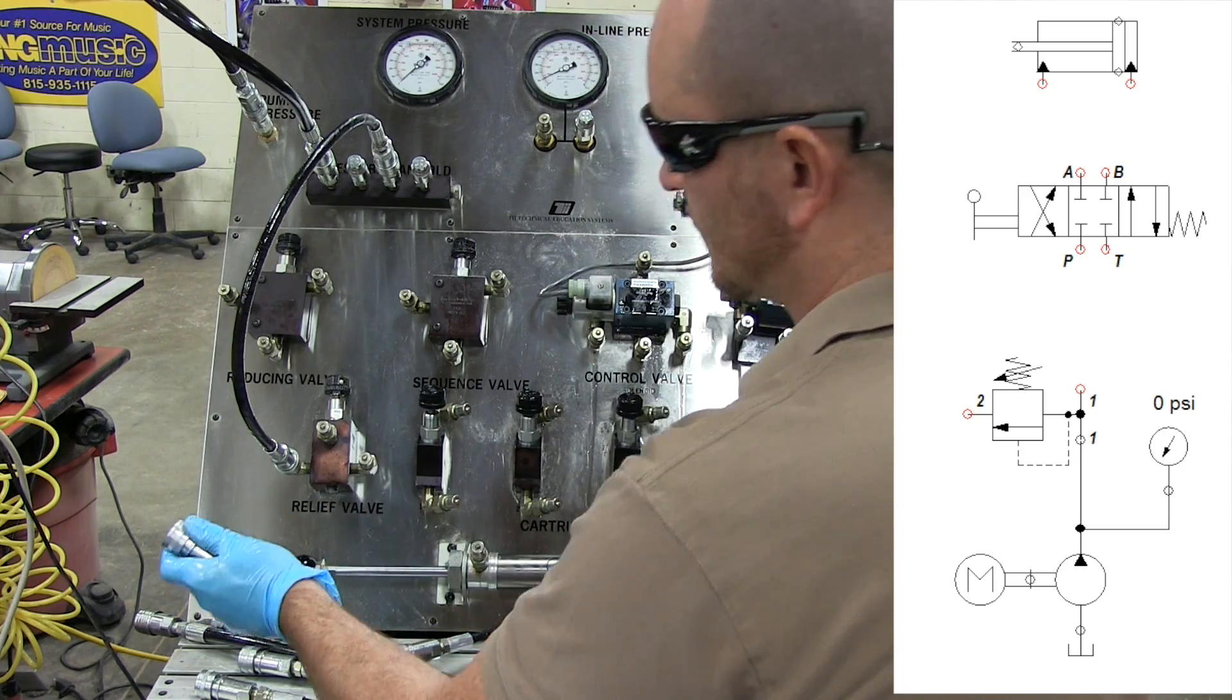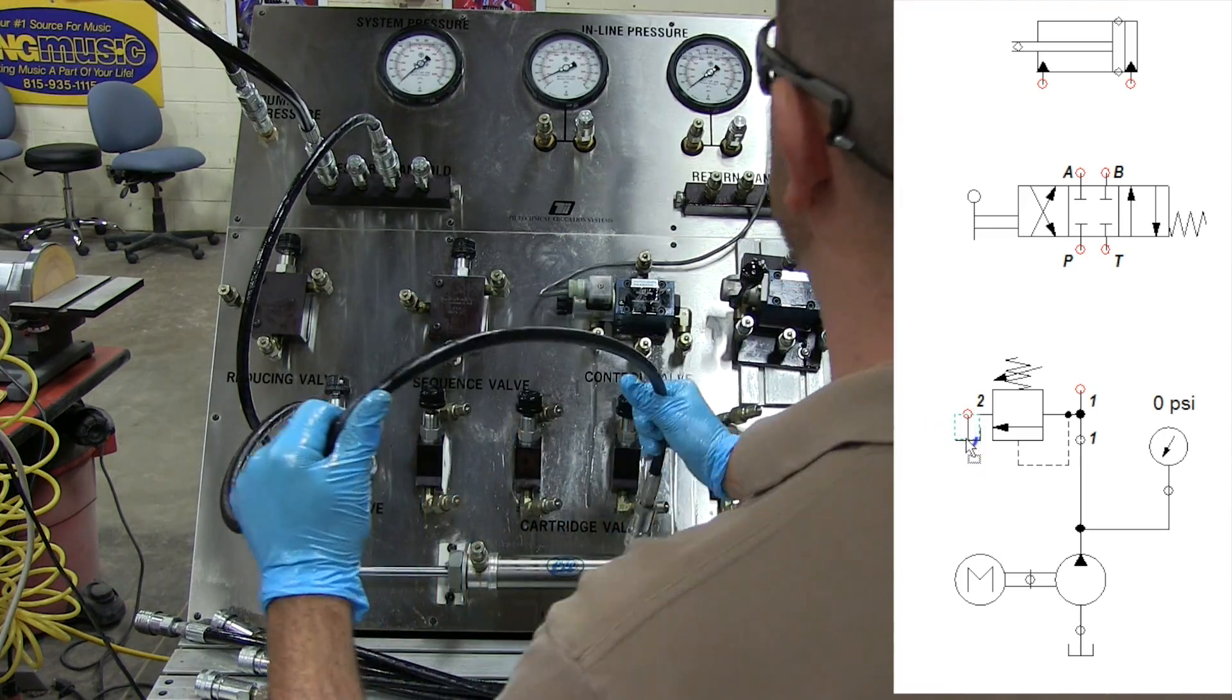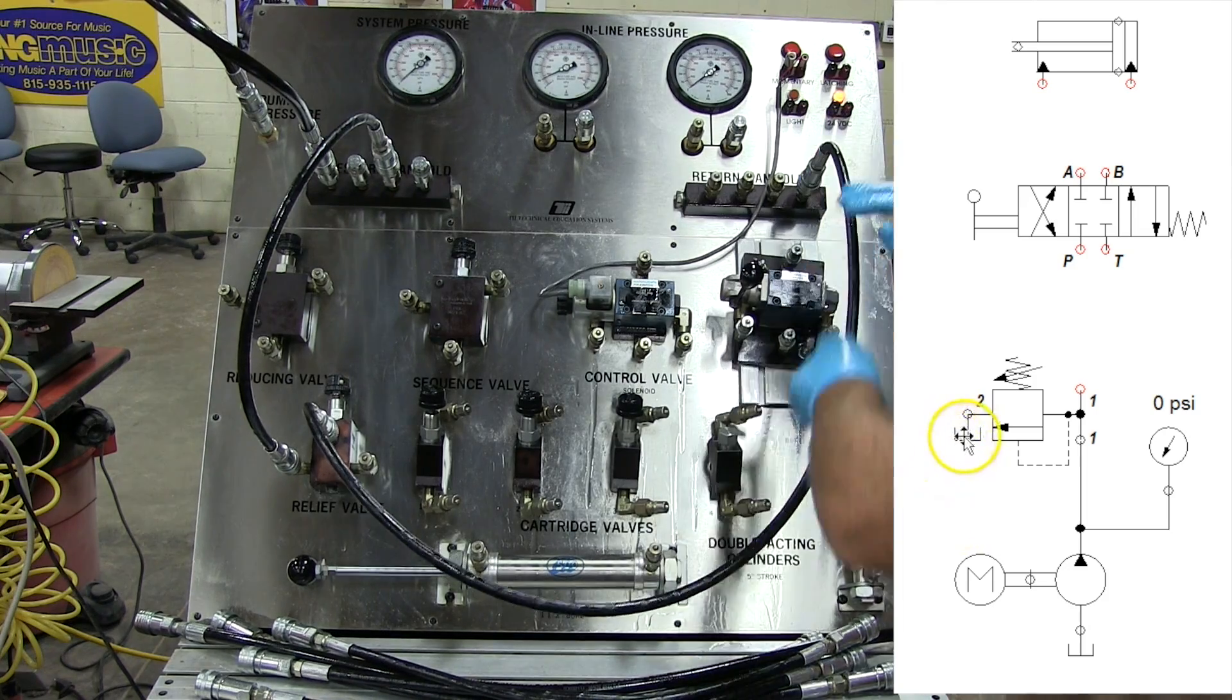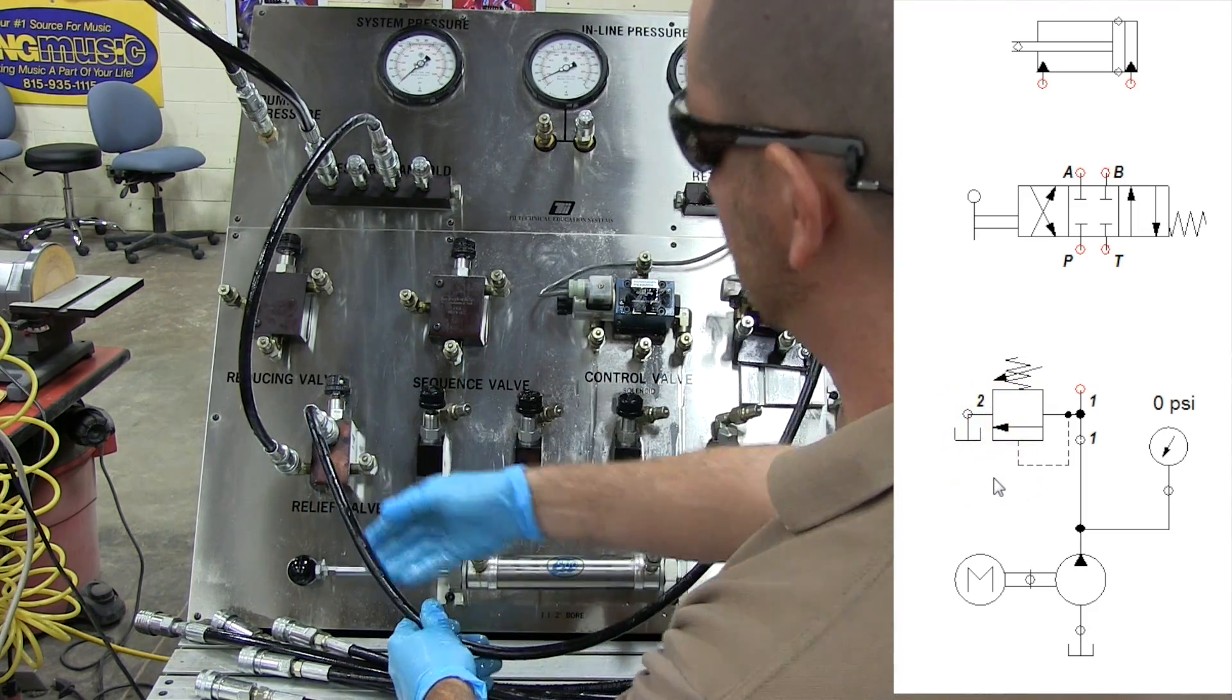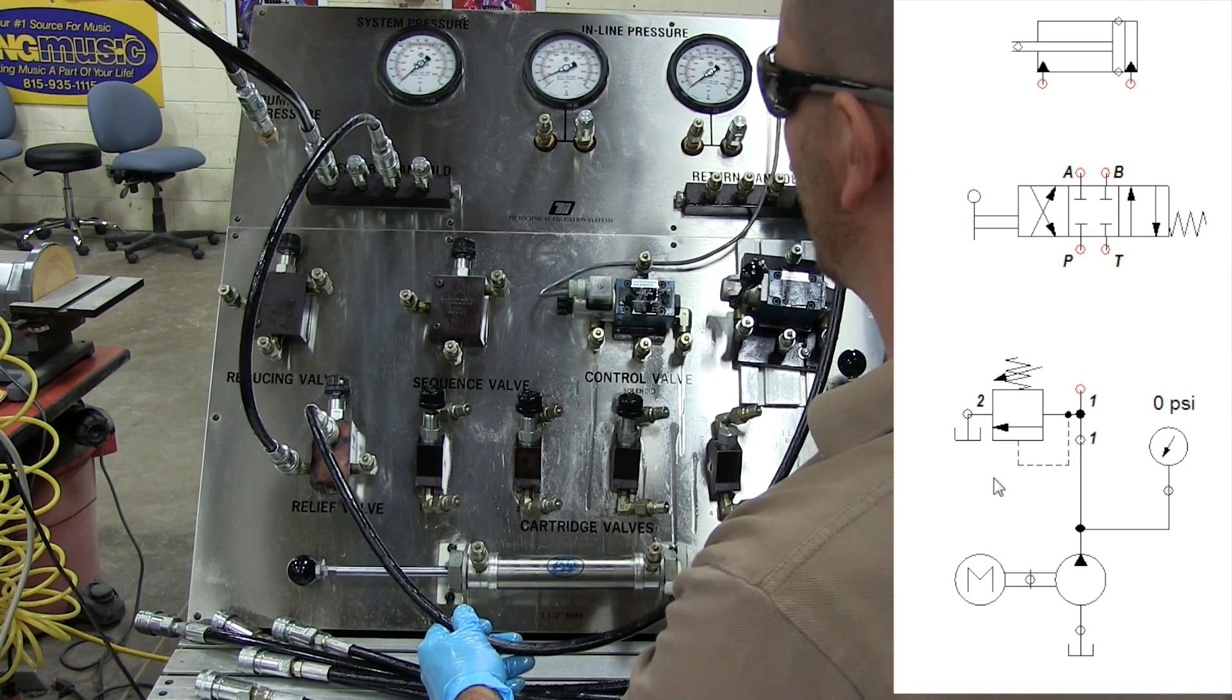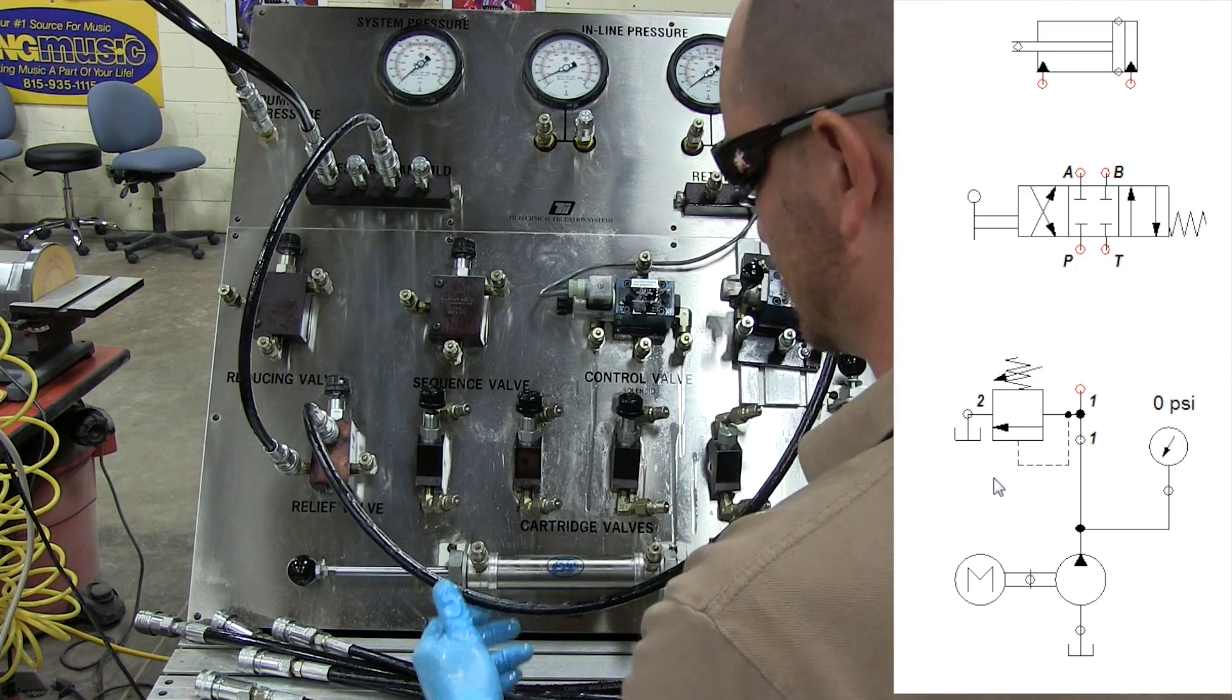So what we always want to do is we want to take our tank port, the one that goes to tank. This will always go to tank. Now schematically this can be deceiving because the tank is always right next to the pressure relief valve, but in real life it's a hose or a pipe or a combination of a pipe and a hose going all the way back to either a return manifold or directly back to the tank, depending on the size of the system.